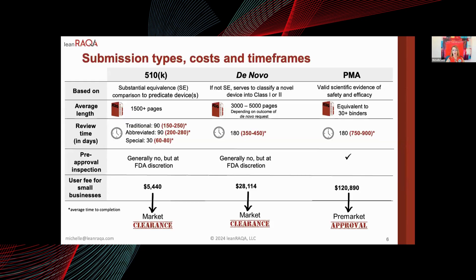PMAs — pre-market approvals — are the equivalent of 30-plus three-inch ring binders. The FDA measures submissions against internal clock days: 90 clock days for a 510k, though the average is about 200 days once you factor in additional information requests. De novos have a 180-day clock with an average of 400 days. PMAs average about 800 days.